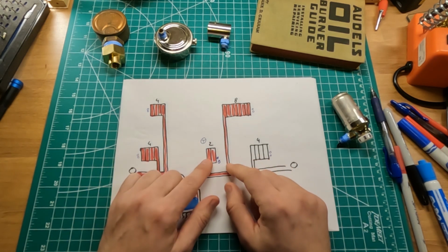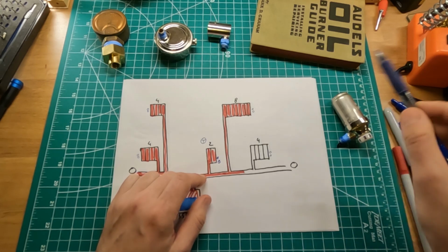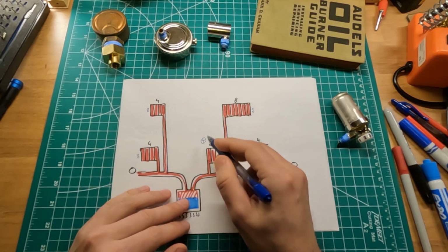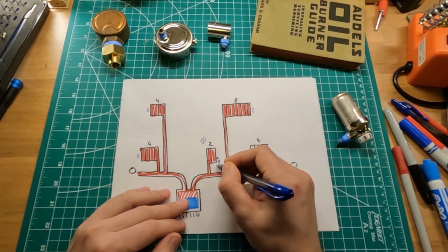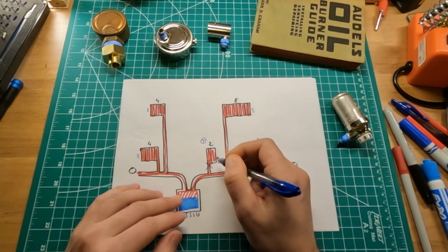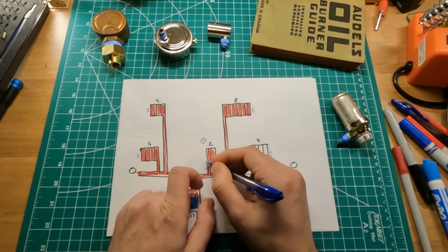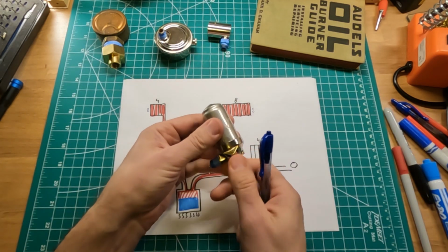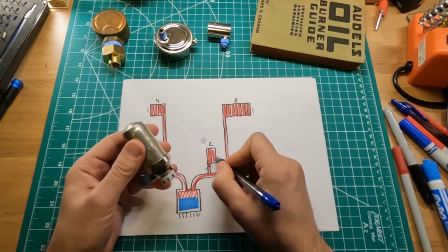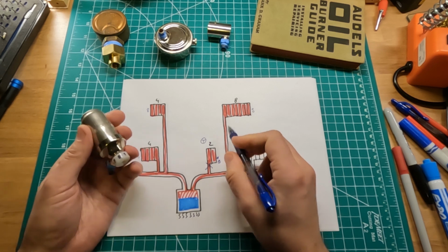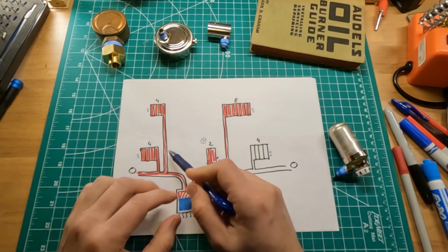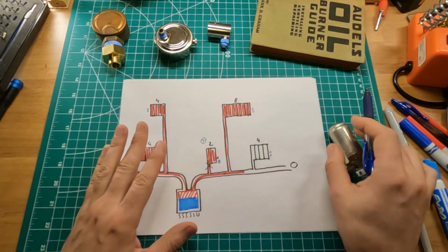Another solution would be to maybe totally close it. Let's say this room was somehow open to other parts of the house or the apartment, then you basically close down this valve right here, a supply valve, so that you can close this radiator down totally, or you can close down the orifice. So you take a vent like this and screw it all the way in, so that nothing comes out through this opening anymore, and then this radiator would never heat up, and this thermostat could be satisfied only via warmth coming from other rooms. So that's a possible solution.